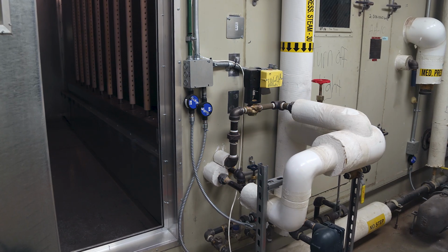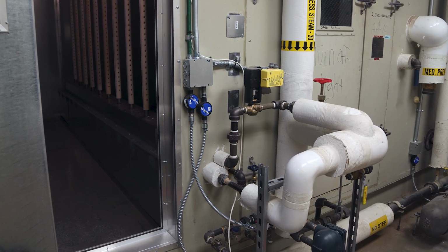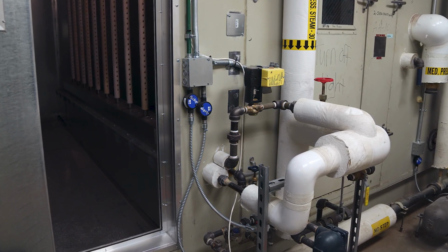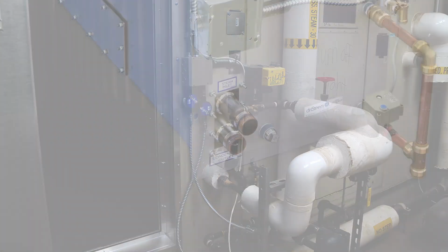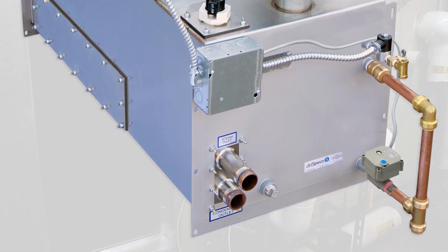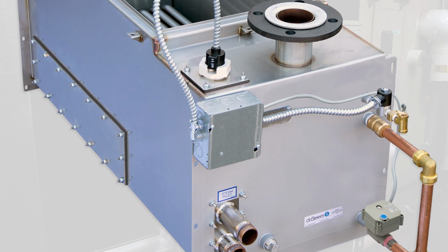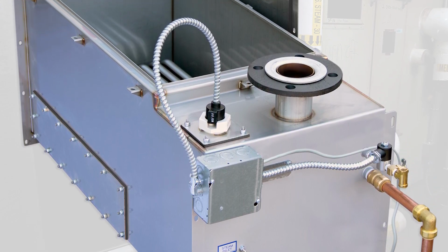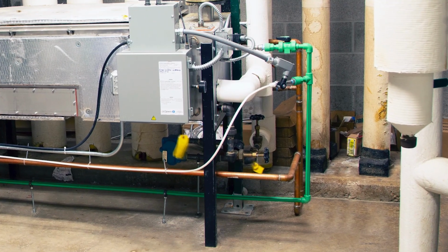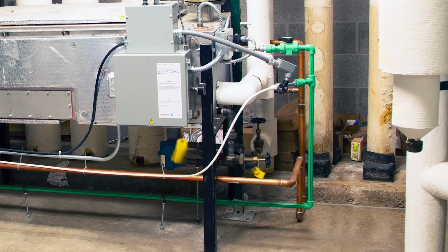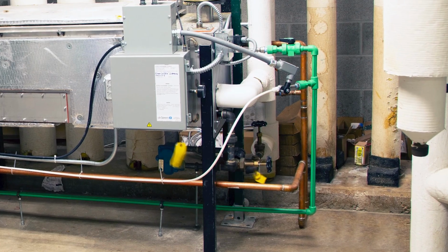If you don't, now we're getting into generation, where we have to make the steam because we don't have it available. Now, if you've got that boiler already available, maybe we can do that indirectly. We can still use it as an energy source. You've got all that energy, the steam already, and send it through a heat exchanger, as an example. But then you have a separate source of water that's being used for humidification. So no more concerns with what's being added to the airstream, because now you've isolated it: what's in the boiler stays in the boiler, and what's going into the airstream is a separate source.